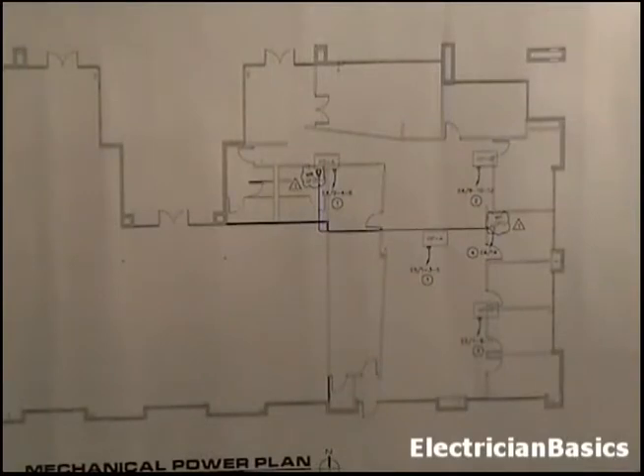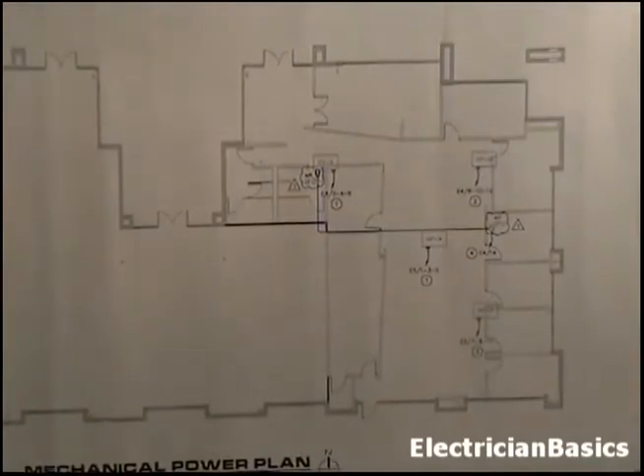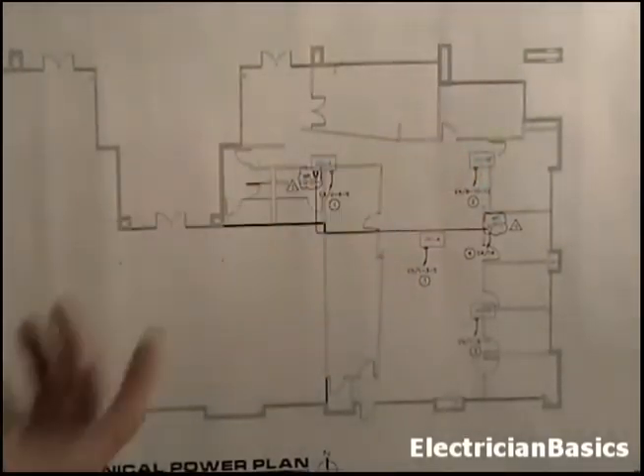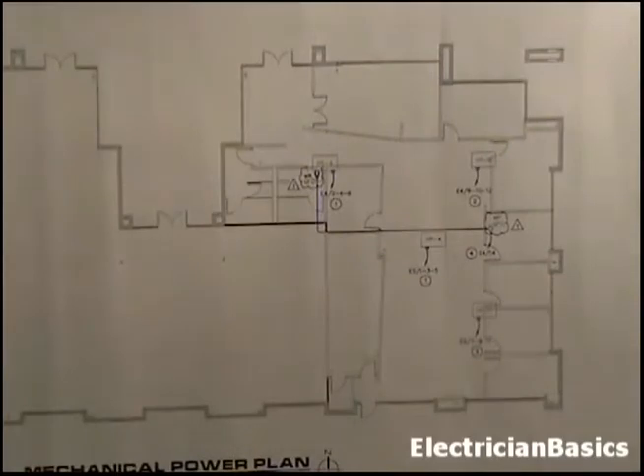Remember sheet M 2.1. We've already looked at the packaged heat pump unit schedule. You can get the model number and all of that, and you can actually find the orientation on the unit and find out where that disconnect should go on that unit. And that way you can properly plan your stub outs. Now the nice thing about these units here is that there's a little cabinet in there, and the stub out actually goes into the unit. You don't have to put a stub out beside the roof and make another roof penetration. So that's what made these units pretty nice.